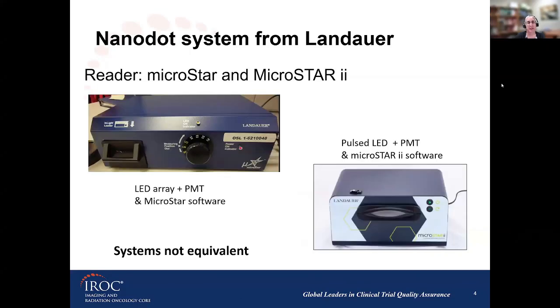The second part of the system is the reader per se. So there are two models that are able to read nanoDots. The first one is the MicroStar model, which is the dark blue reader on top of the image, and MicroStar II, which is the latest one, which is on the bottom. The reading engine on these two readers is based on an LED plus a photomultiplier, and each one of these readers has a dedicated software to take readings and process dose calculation. But I would like to make the comment that these two readers are not compatible. The reading engine is completely different from one to the other, making these two systems not equivalent. So calibration from one cannot be transferred to the other reader.